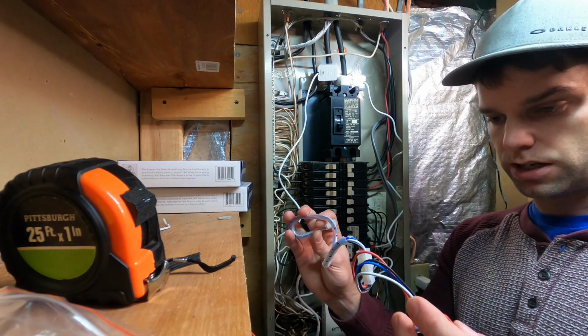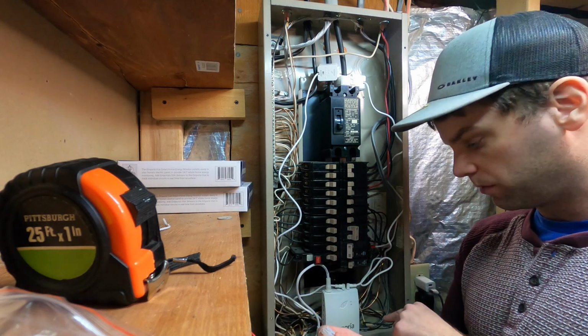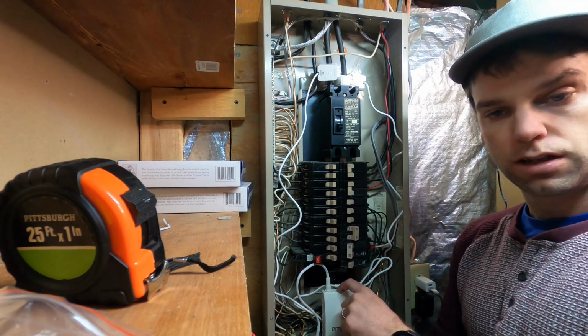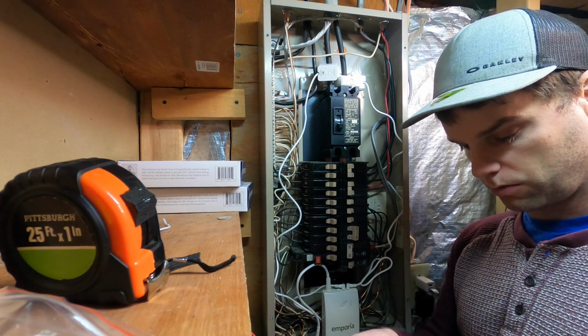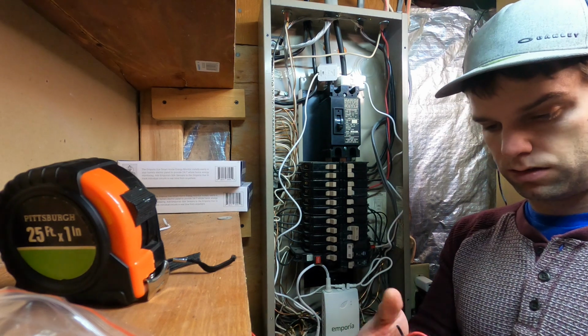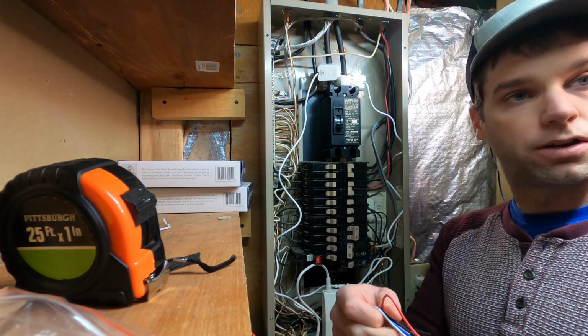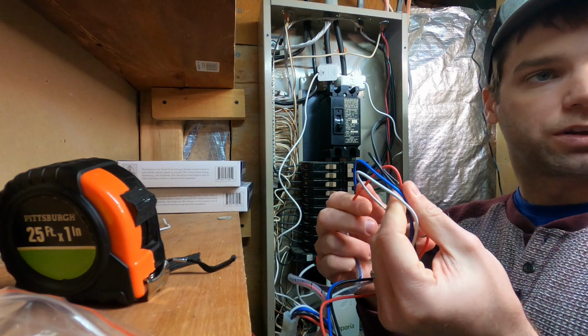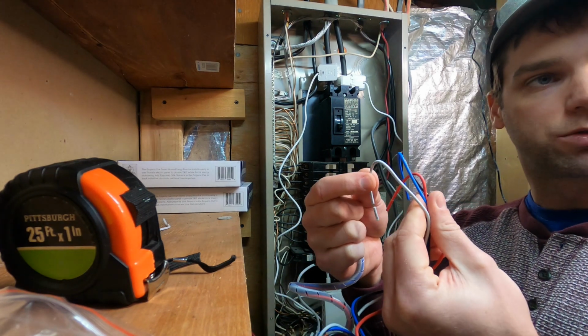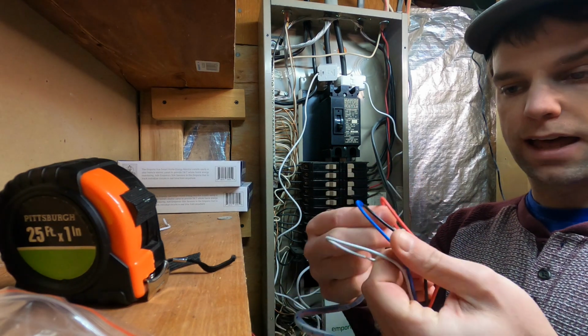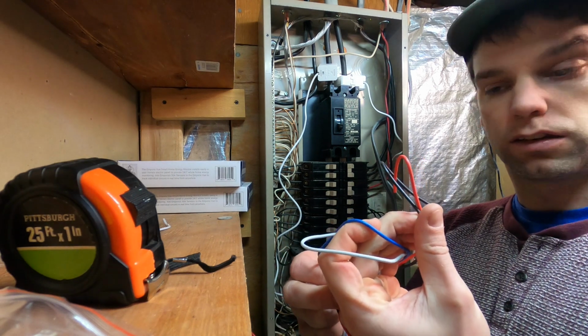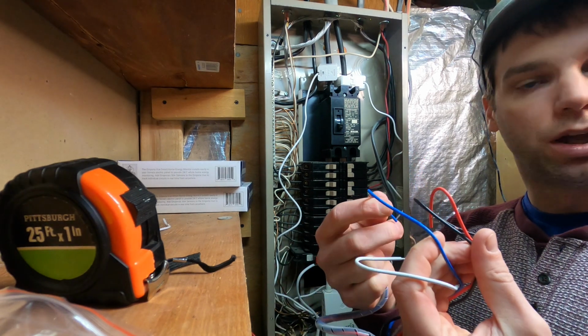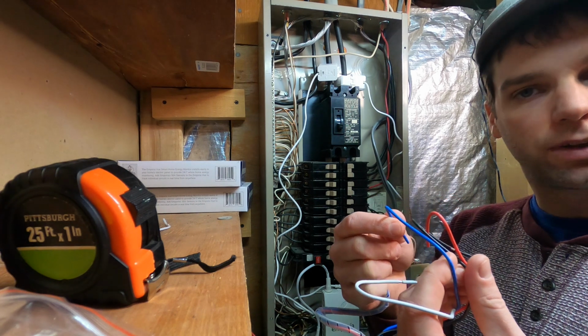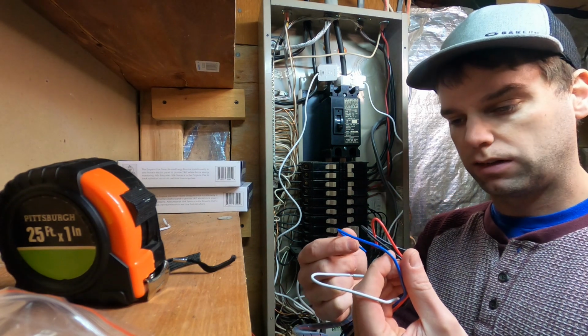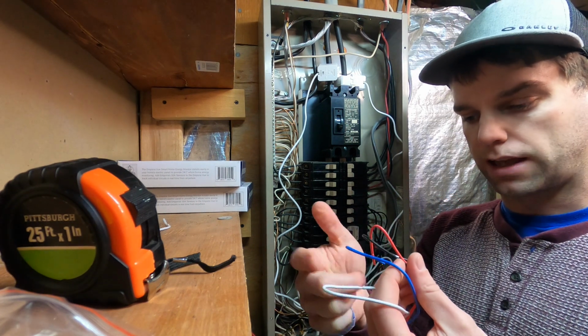So we have to hook this unit up to the bottom of our main unit, and then we're going to provide it power. We have four wires with this unit. White, which will be our neutral. Red and black, we traditionally see as our hot wires. And then they also have a blue. The blue, I think, is for if you've got three-phase power. Again, we don't have three-phase, so we're only going to use red, black, and white.